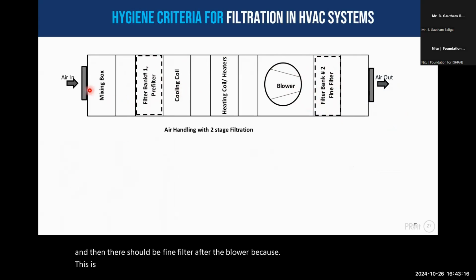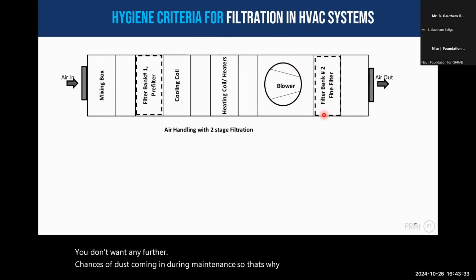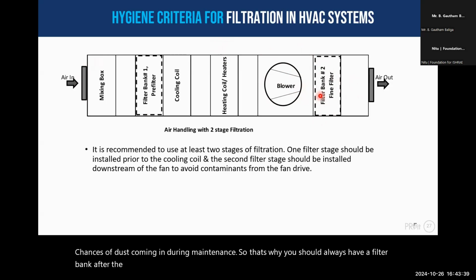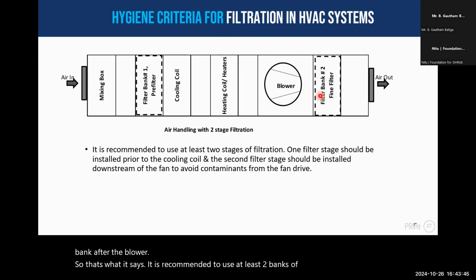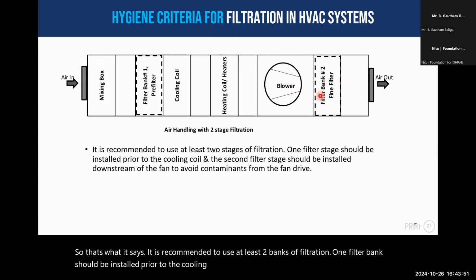This is because right up to the blower, all these are high maintenance areas, and after filter bank two, you don't want any further chances of dust coming in during maintenance. So that's why you should always have a filter bank after the blower. So that's what it says. It is recommended to use at least two banks of filtration. One filter bank should be installed prior to the cooling coil, and the second filter stage should be installed downstream of the fan to avoid contamination from the fan drive.